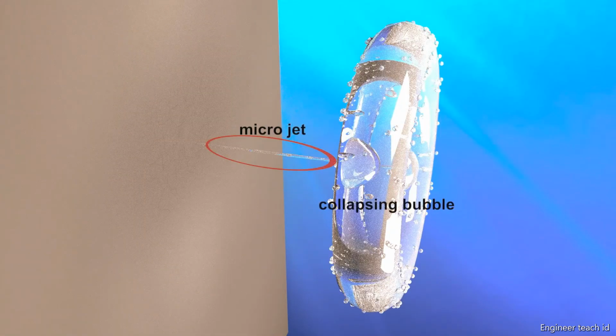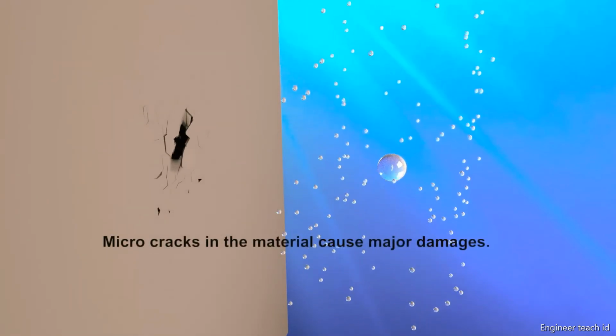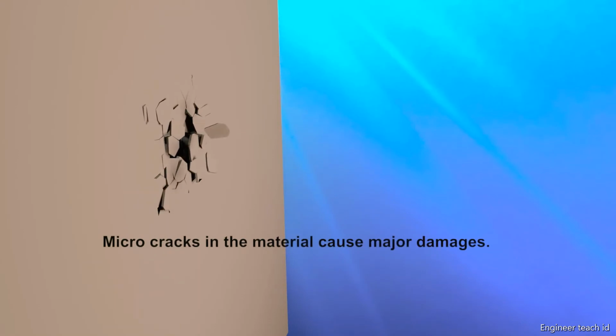The implosion releases energy in a very short time concentrated in a very small spot. If the microjet hits a surface, it damages the material by a localized short-term overstraining. The material starts to evolve microcracks, and later material can break off. We show a few examples of damage in pump impellers kindly provided by the Swiss pump manufacturer Häny AG.